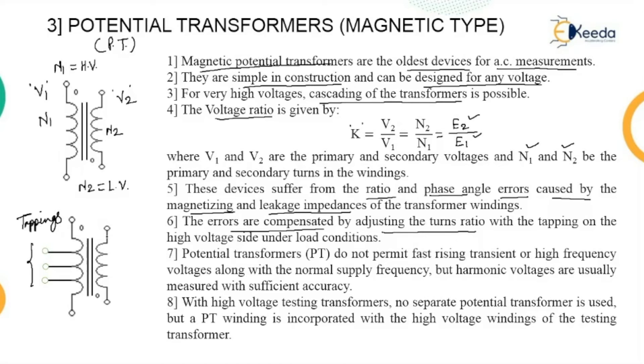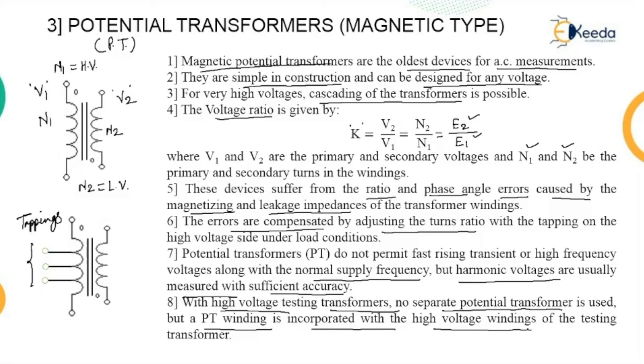Potential transformers do not permit fast-rising transients or high-frequency voltages along with the normal supply frequency. However, harmonic voltages are generally measured with sufficient accuracy. With high voltage testing transformers, no separate potential transformers are used; instead, the potential transformer winding is incorporated with the high voltage windings of the testing transformer.